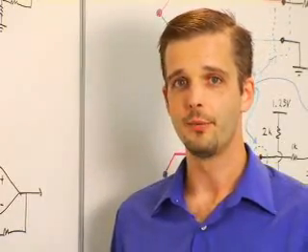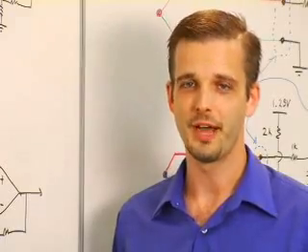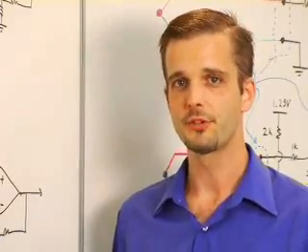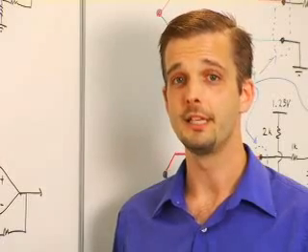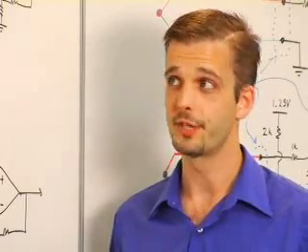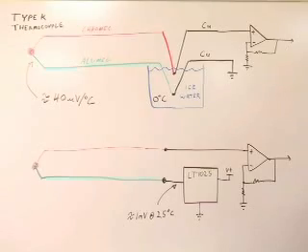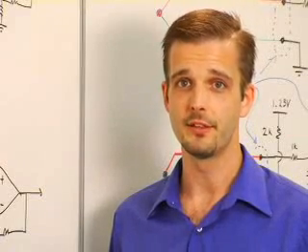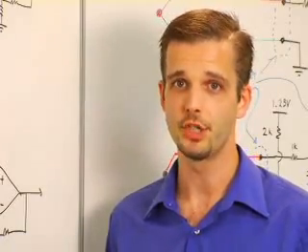Temperature is arguably one of the most measured physical phenomena, and there's a lot of sensors to choose from. Thermistors are highly sensitive, and platinum RTDs are very stable and accurate over time. But thermocouples, in spite of the fact that their accuracy is quite low, a few degrees centigrade, and the output voltage is quite small, microvolts per degree C, they still find wide application because they're very rugged and very cheap.